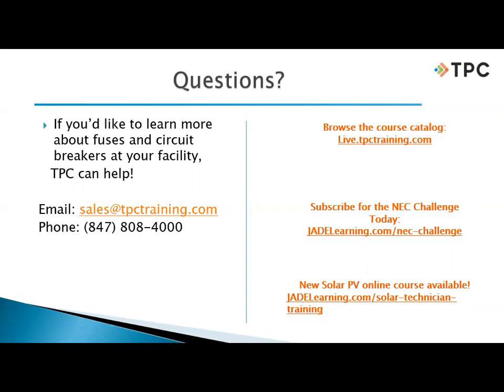A lot of people are curious about the maintenance side of these circuit breakers, with a lot of technicians here. One particular question I see coming in is the number of trips. What do you find some of the manufacturers tend to average on the number of times these circuit breakers can be actuated and tripped before they should be replaced?